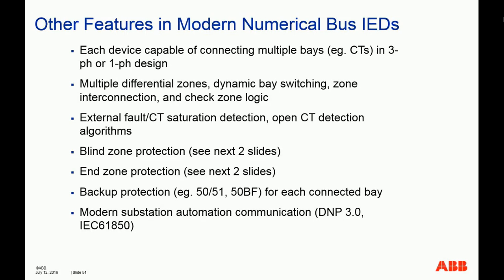So for single phase design, obviously you will have 3 boxes, each making their own decision, but the advantage of that is that you increase capacity. For example, if you can connect 8 three-phase CTs in one box, you have that capability in your analog input I/O modules. Then that means for a single-phase design, you can actually connect 24 single-phase CTs because 8 times 3 phases. So in other words, you can protect 24 feeders with 3 boxes in this type of low impedance system. Okay.